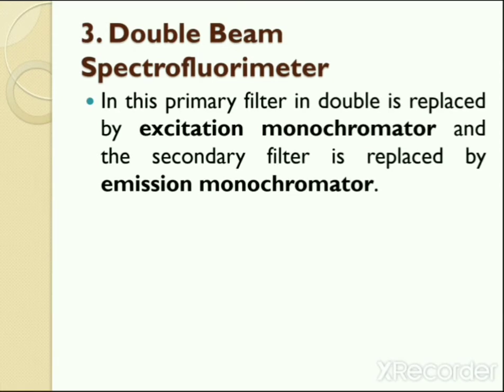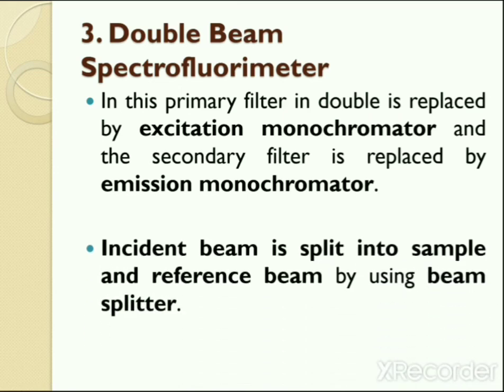The most advanced type of instrument used in fluorimetry is the double beam spectrofluorimeter. In this type, the primary filter is replaced by an excitation monochromator and the secondary filter is replaced by an emission monochromator. The work of a monochromator is to convert polychromatic light into monochromatic light; they can isolate a specific range of wavelength or a particular wavelength of radiation from a source. The excitation monochromator provides suitable radiation for excitation of molecules, while the emission monochromator isolates only the radiation emitted by the fluorescent molecules. In the double beam spectrofluorimeter, the incident beam is split into a sample beam and a reference beam using a beam splitter.